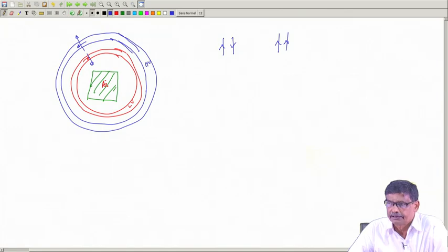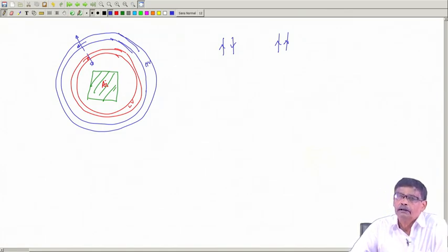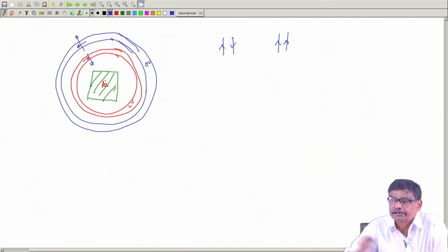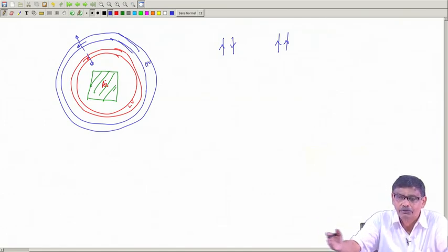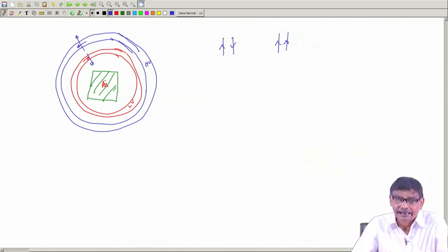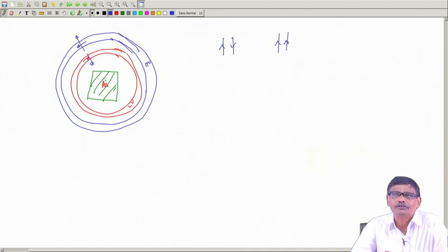rated currents at least. But what happens is this, you do not know, there might be a short circuit taking place and a very large current flowing. Then this force will become enormous and the HV windings will become loosened and come out. That is why protection of the transformer is so important.